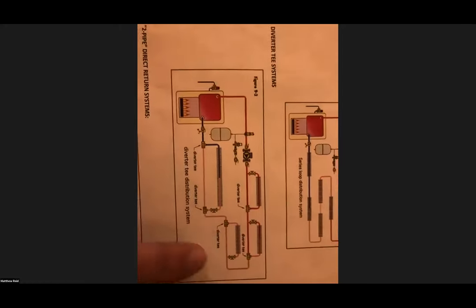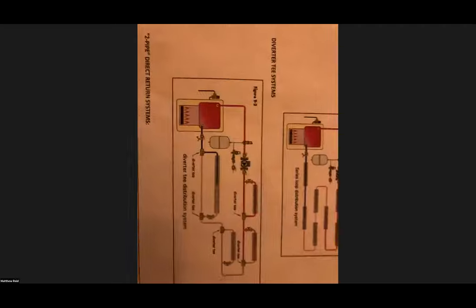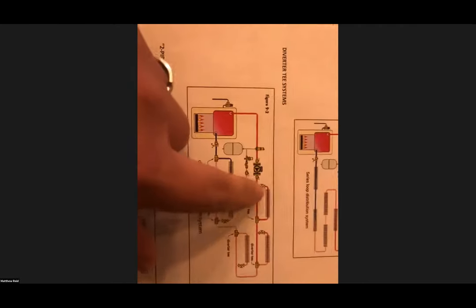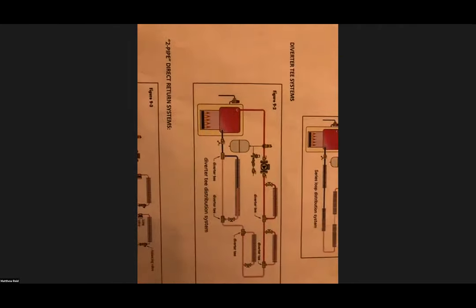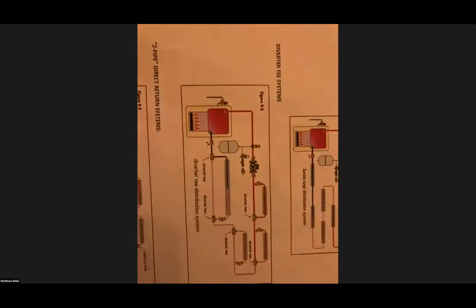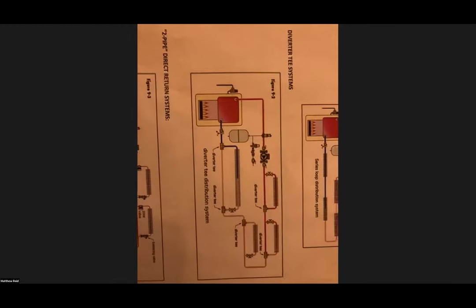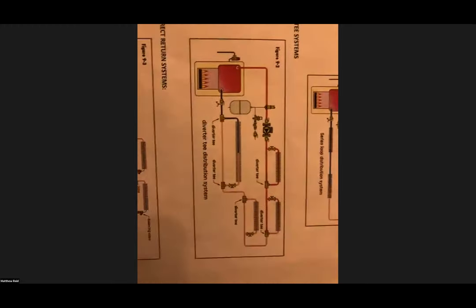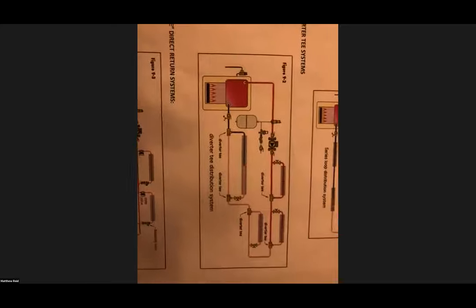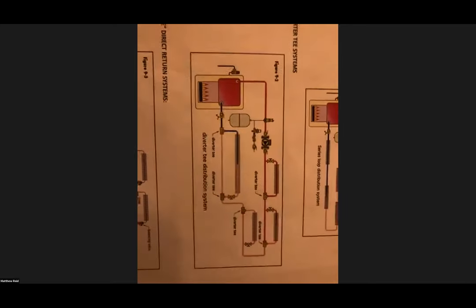Next system, we have standard in and out, but we now have monoflow T's. These T's combined with rad valves will provide that we have the water going to the rads that we want and make sure that we're ensuring flow through those rads. We don't see them a ton anymore, but it does still come up from time to time. And again, this is what we want to talk about for the things that you're seeing when you get into a system. So we want to be familiar with, yeah, okay, I've seen this before. I know that this works. Or I've seen this before and it's piped wrong, so I know what I can do to get this particular system to work again.